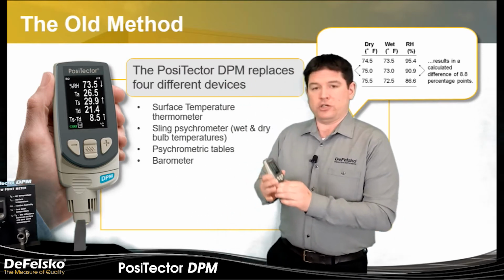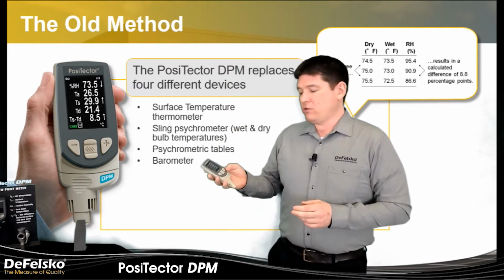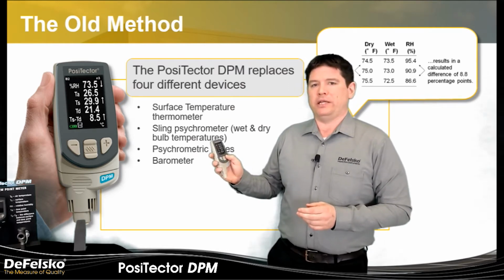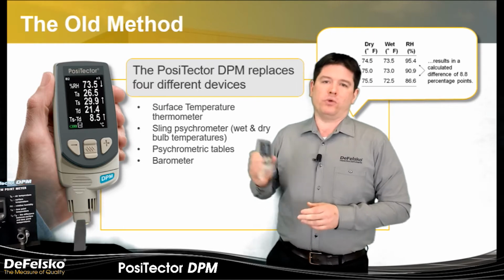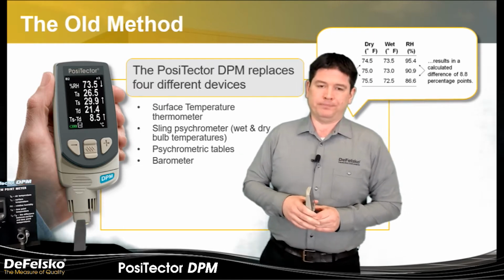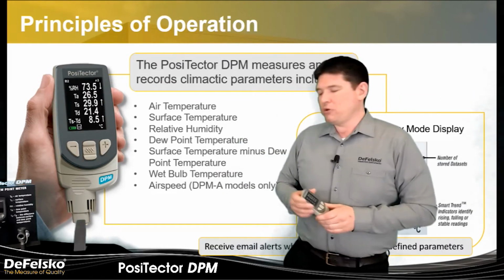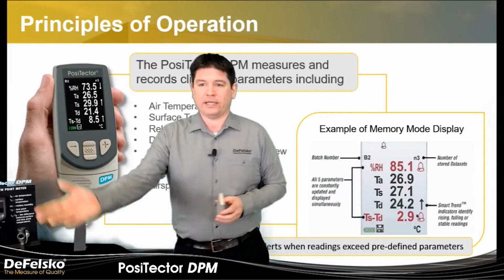You don't have to make a judgment call. And when you want to take the reading, you push the plus button on the gauge. It stores the data set into memory. There is no guesswork. You can then use that on a report down the road.